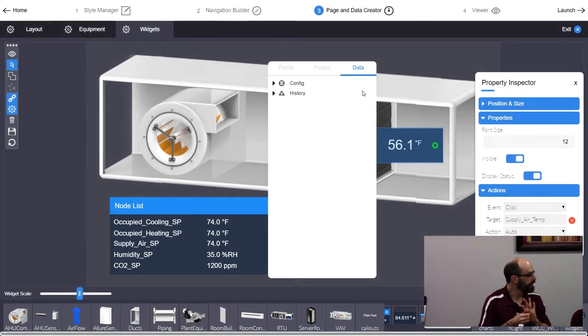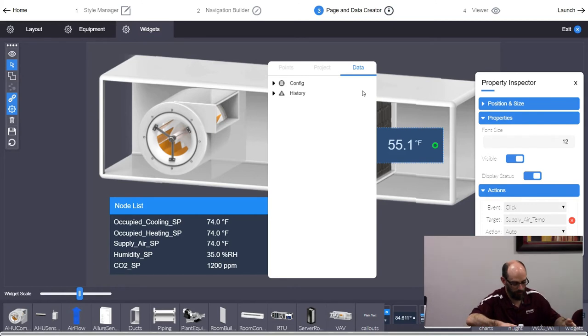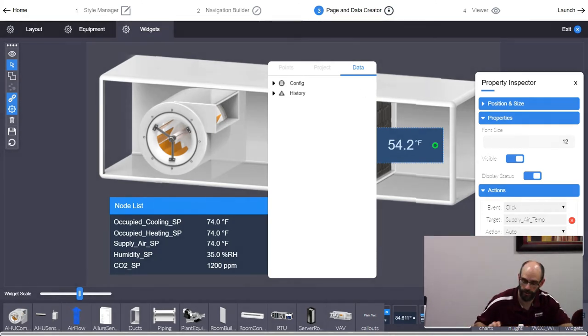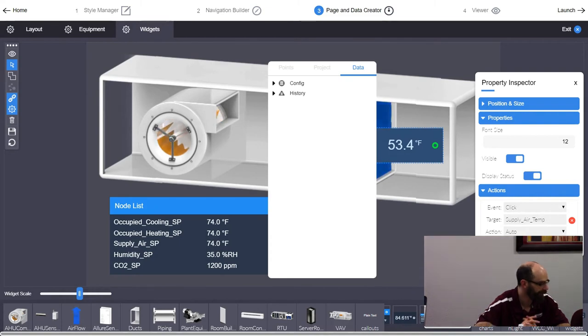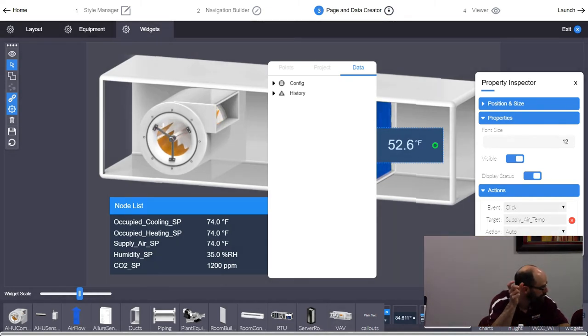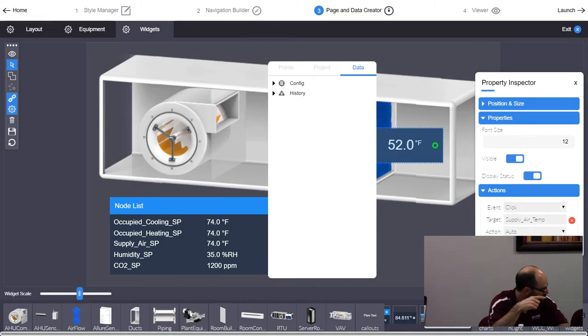If you want the value relativized — updating per controller — pull it from the points list. If you don't want it relativized — for example, a value that's the same reference across every record like outside air temperature — pull it from the data tree. It will still update to whatever that fixed point's current value is, but it won't change which point it's looking at as you navigate between controllers.